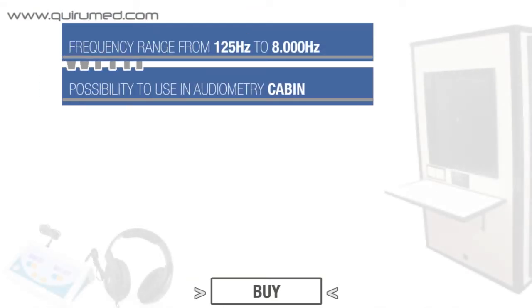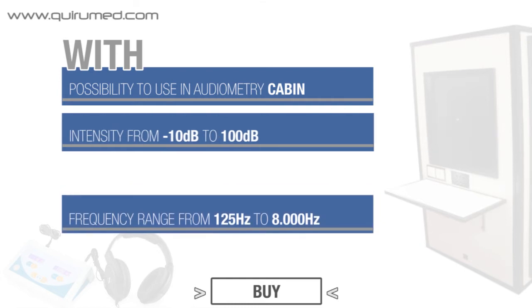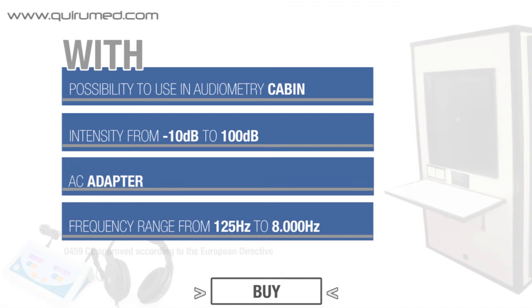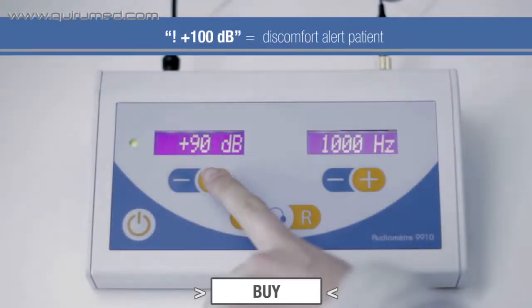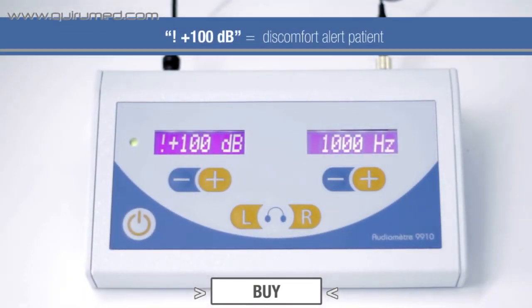It can be used in audiometry cabins, with a frequency range from 125 to 8000 Hz and intensity from 10 dB to 100 dB, and it works with an AC adapter.